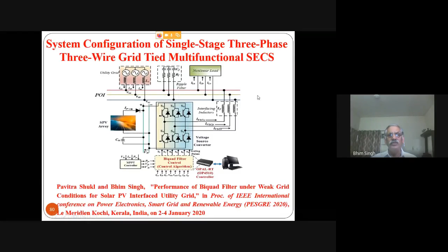But depending upon this impedance and this impedance, you will certainly get switching noise created by the inverter at the point of common coupling. To improve that voltage profile, you have to keep this ripple filter. Losses in the ripple filter, irrespective of the rating, are not more than 2-3 watt, because the resistance we keep is around 5 to 10 ohm and the capacitor value is around 5 to 10 microfarad. At fundamental frequency it offers a very high impedance, so the current is very small. But at the switching frequency, where you don't have too much power, it has a very low impedance and absorbs it. So all switching harmonics go virtually into that, and you improve the voltage profile.